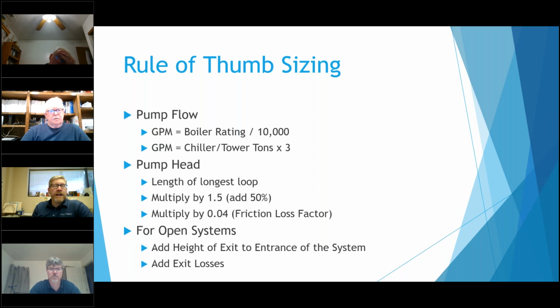And then for the pump head, I try to figure out the longest loop. So you're thinking, well, the pump, it's about 100 feet that way, it's going up 30 feet, and it's coming back down 30 feet, and it's coming 100 feet back. You estimate what that longest loop might be, multiply by 1.5, and that usually gives you a good rough estimate as far as a safety factor, as well as adding more pressure drop, because valves and T-fittings and elbows and everything like that do all add more pressure drop to the system. So that gets added in that extra 50%.